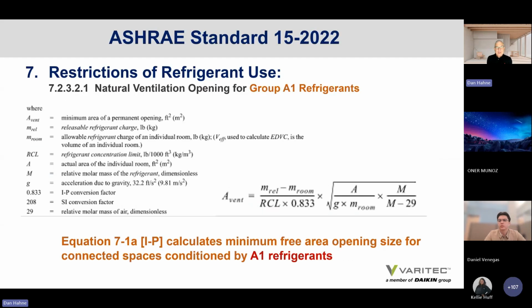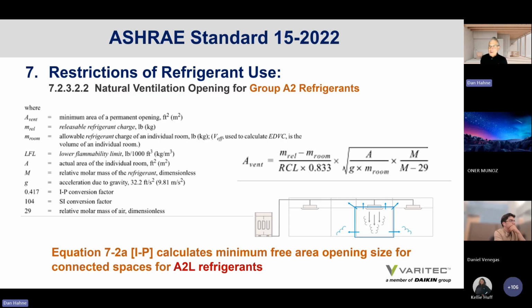And here are the equations in the standard that show how that minimum free area of opening is to be calculated. This represents group A1 refrigerants. Notice that the assignment of that free area for group A1 refrigerants is a different equation from the assignment for group A2 refrigerants. So if you're designing to A2Ls, which you very likely are, remember that the free area of the openings that define a connected space have a different equation, and it's defined by section 7.2.3.2.2. So be aware of that.